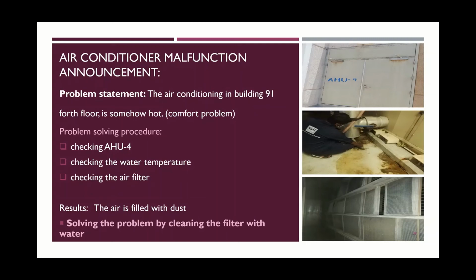First, we went to AHU4, which is the AHU responsible for the air conditioning on the fourth floor. Before that, we checked the water temperature to make sure that the problem was inside the AHU itself, not from the distribution station. We checked the water temperature and it was good. So the problem was inside AHU4.